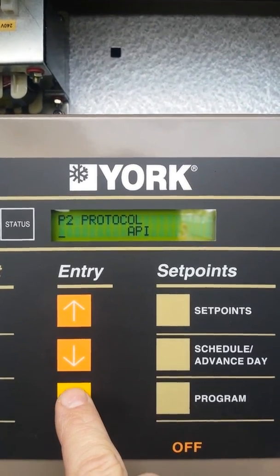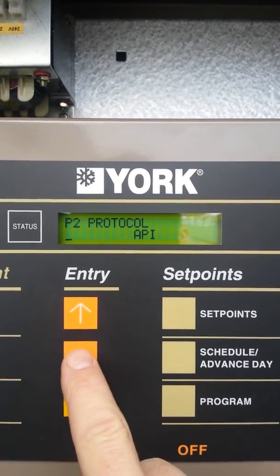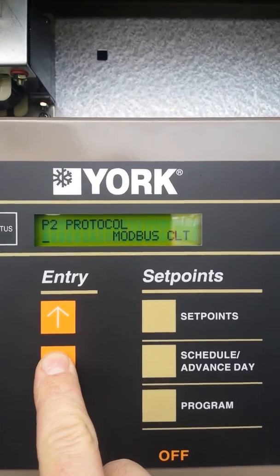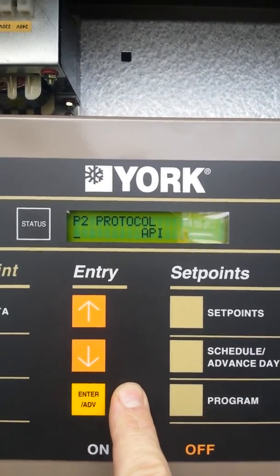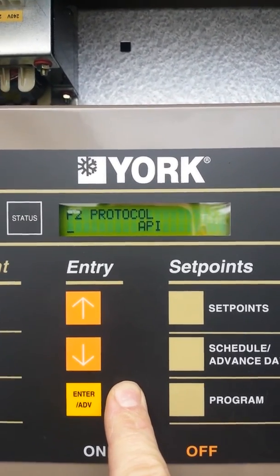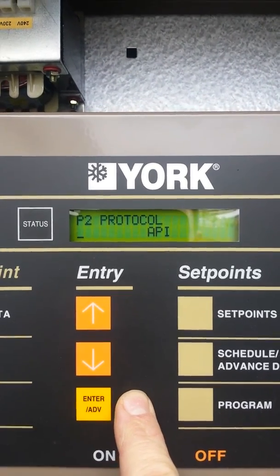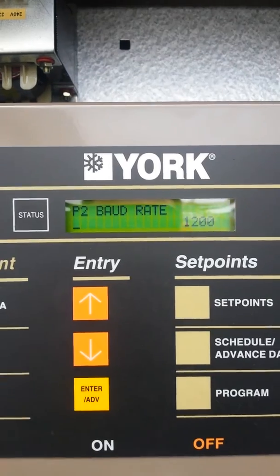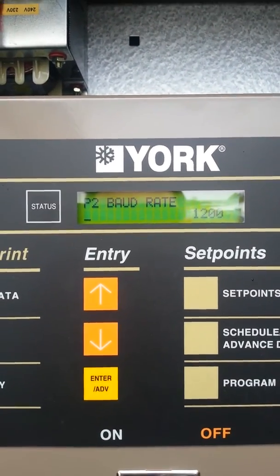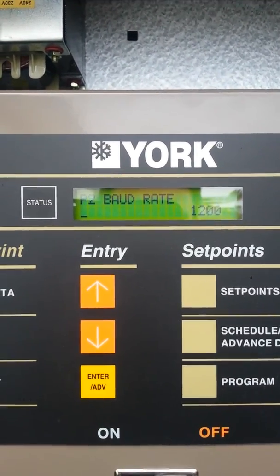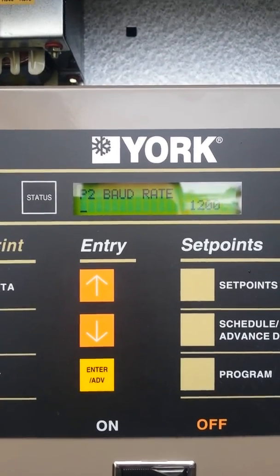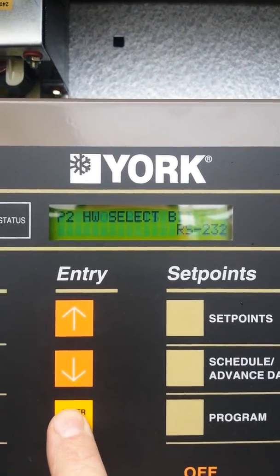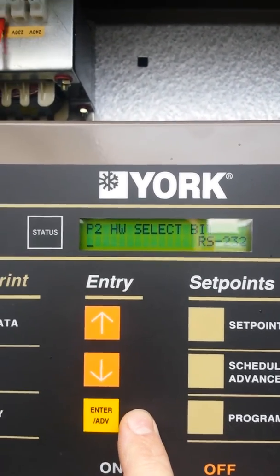P2 is primarily for port 2 and can be set up for different things: Modbus, unavailable, IO, terminal, and so on. I have it set to API because if this thing faults or I want to do a maintenance check, I can hook up my laptop and print off faults and running operation data. The MAC address doesn't really matter on this one. I set the baud rate to 1200 because when you use a printer port with your computer, you've got to match all the baud rates — the program and the cable that communicates to the device all have to be set at the same baud rate so it all communicates effectively. P2 parity, stop bits one, and RS232 because that's what we use for the printer port.